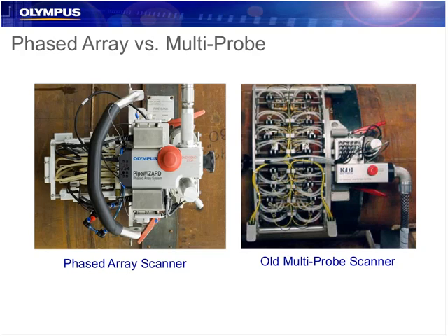So these would have 20, 30 some transducers that we would try to position very, very accurately in order to have one single conventional beam hitting our required zones. We can imagine the trouble with this, very precise. We have many, many different parts that can move. If one transducer becomes misaligned or if the scanner's dropped, we're basically not getting the full coverage of it.